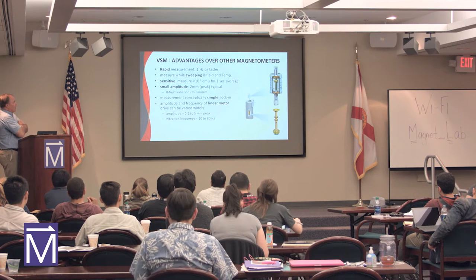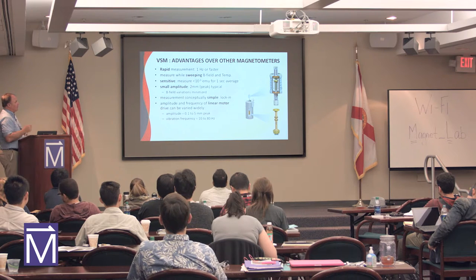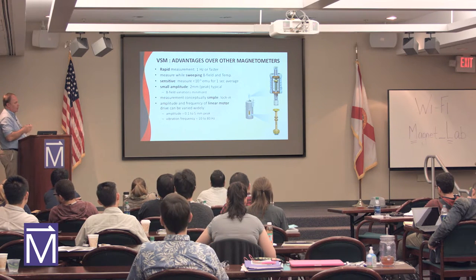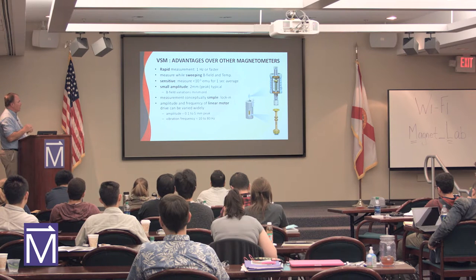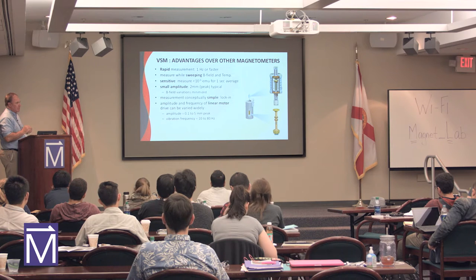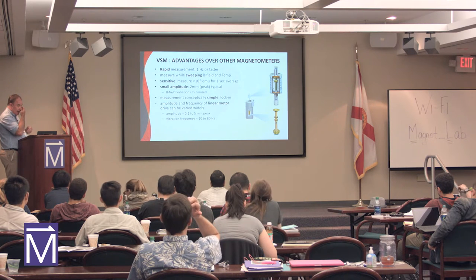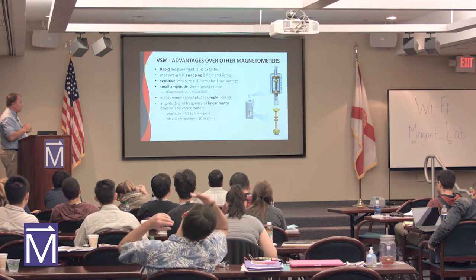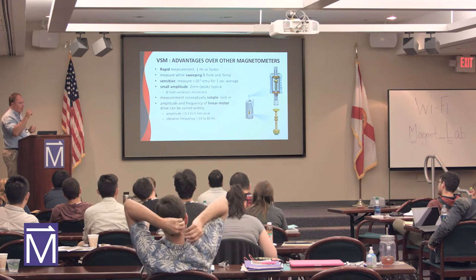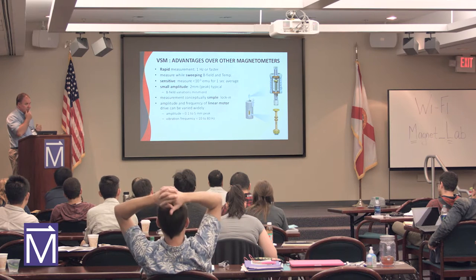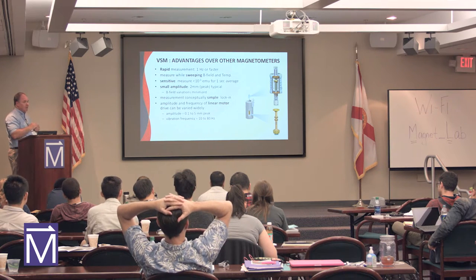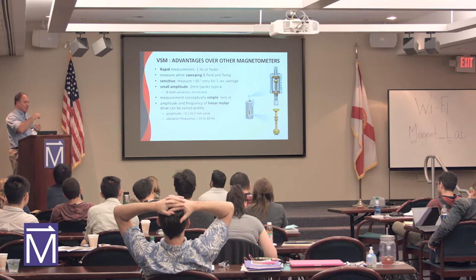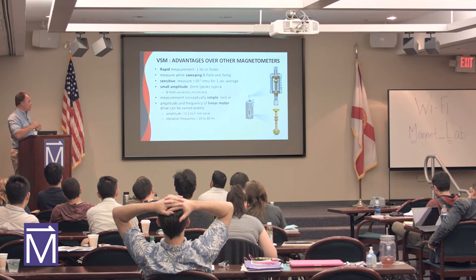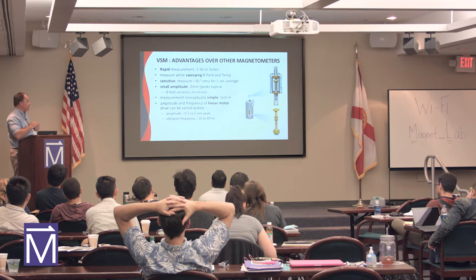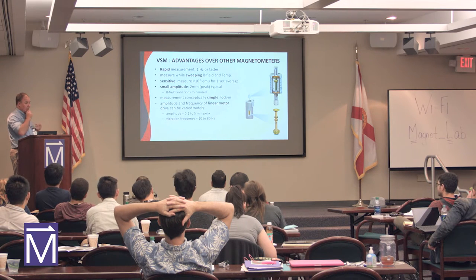So the VSM over other types of magnetometry: fast measurement, the sample's moving fast through the magnetic field. You're taking measurements while you're sweeping the sample through the field. 10 to the minus 6 EMU in a less than a second measurement time, so it's a sensitive measurement. You're moving it through a small amplitude, so it's only moving a couple of millimeters through the magnetic field. It's in a homogeneous part of the field, so the field distribution variations are eliminated because it's in the homogeneous part of the field.